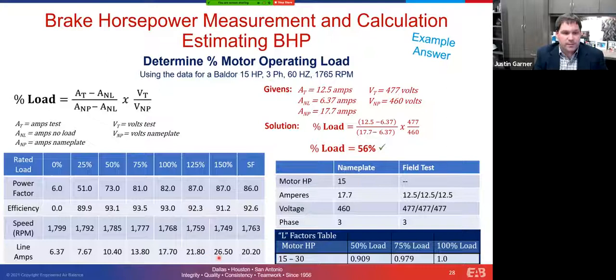We always try to suggest to folks not to put things into that application because you are going to affect the life cycle of the motor itself. And obviously if you exceed service factor, more than likely you're going to do permanent and irreparable damage to the motor, maybe not immediately, but you're going to drastically reduce the service life of that piece of equipment, depending on the application. So I hope that answers that person's question.